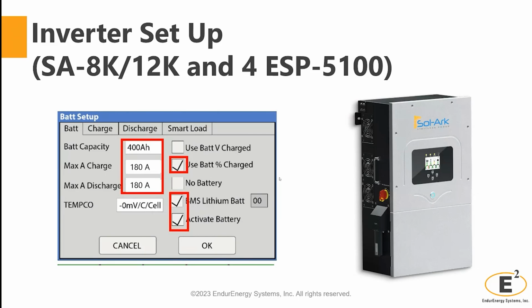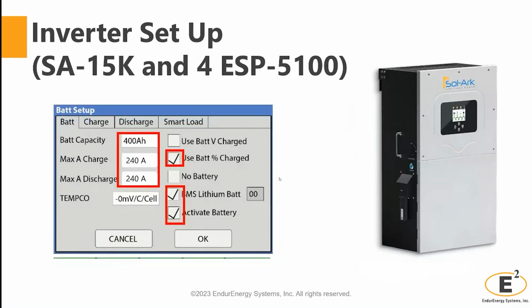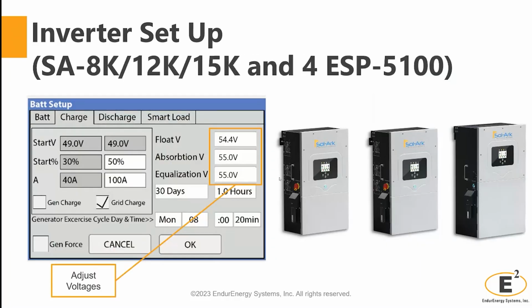When you change to the 15K, the charge and discharge limits change—you can have up to 275 amps. In this case, you can actually use the 240 amps our batteries can sustain without any issue. So you need to change the max charge and max discharge to 240, and activate the selection boxes for use battery percentage charge, BMS lithium battery, and activate battery. Once you finish that part, this is the only thing that changes between the 8K, 12K, and 15K. But once you set up the battery settings, you also need to set up the charge settings for the batteries.